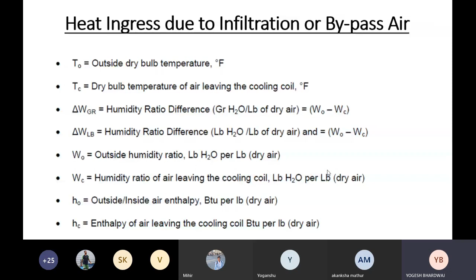I don't add the hot air in my room. If I need to add some fresh air, I will directly push this fresh air at the suction of the cooling coil. So it comes into the room only after getting cooled. Even in that case, some hot air bypasses our cooling coil, like I told you in the last webinar. That's why when I'm putting some fresh air intentionally at my coil, then for 90% of the air I will use my third equation, 4.5 into CFM into enthalpy difference, because this 90% of the air will come into contact with the coil. So I will directly calculate the coil load.